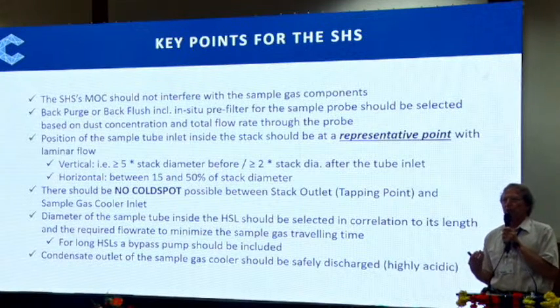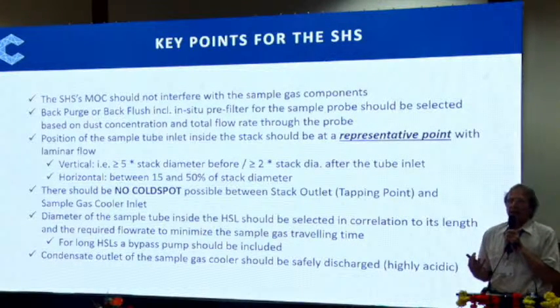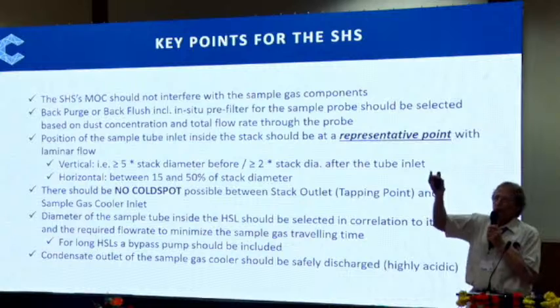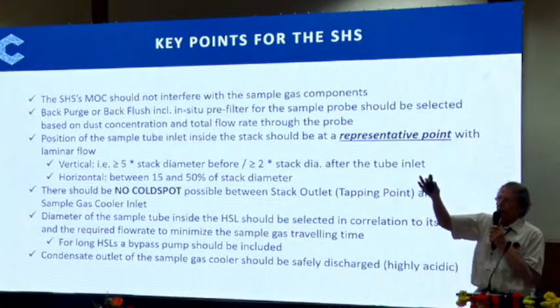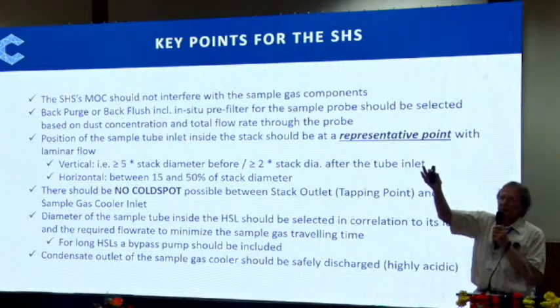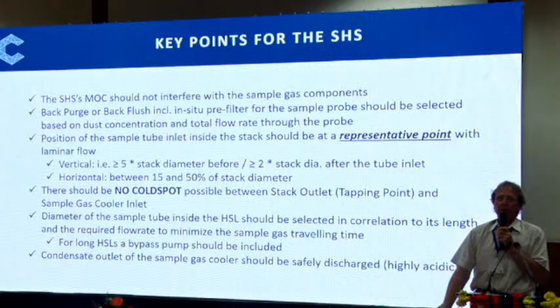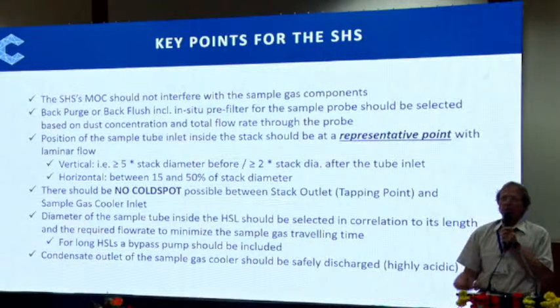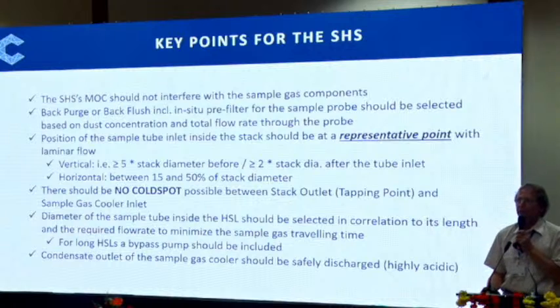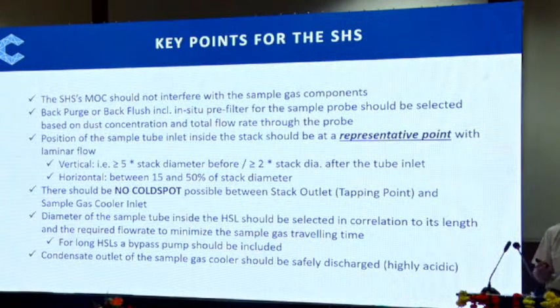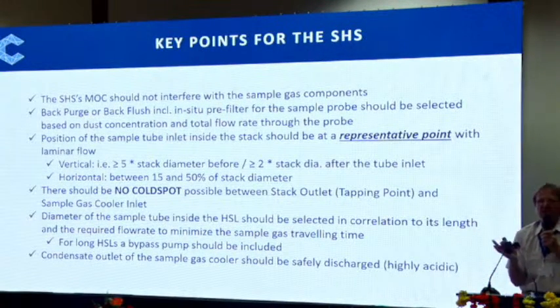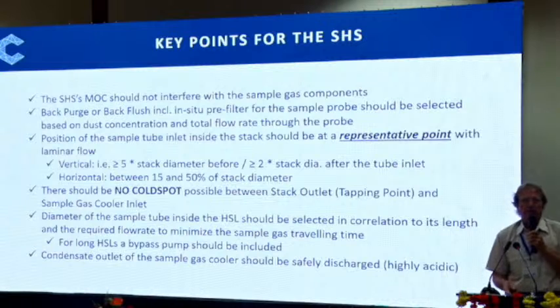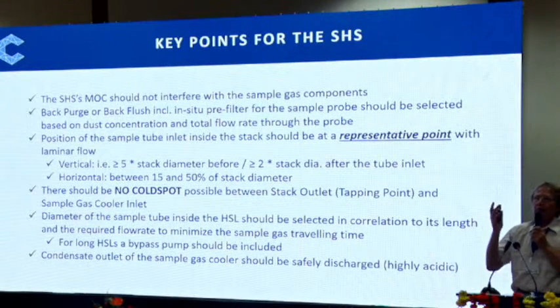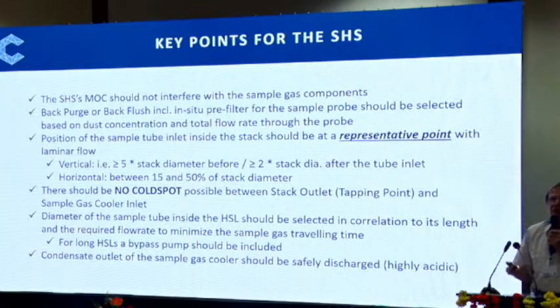Why not closer to the wall? In large stacks, you see an airflow from the stack outlet along the walls, an airflow coming down. So you have a completely different situation directly at the wall in the first, let's say, 5% of the diameter. You have a different flow direction and you have a relatively clean airflow.